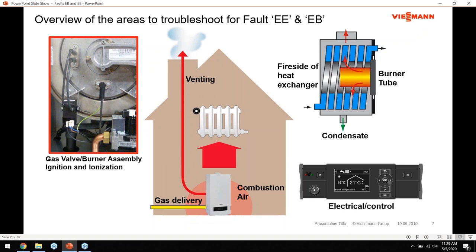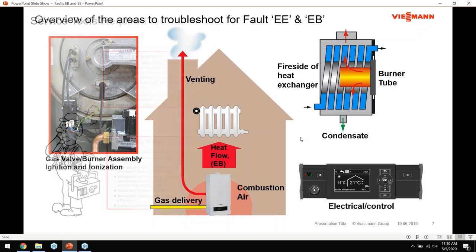For EE faults, the electrical and control side also matters - field wiring to the boiler can have an impact on EE and EB faults. We'll talk about how to check wires and cables for loose connections, and also how to use the boiler's own control as a troubleshooting tool, kind of like a screwdriver in your toolkit. We'll navigate through the controls to get a better understanding of how to use them when troubleshooting.